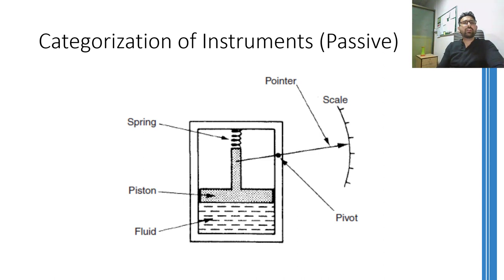The image shown over here is a schematic of another passive pressure measuring instrument. You can see that whatever pressure this fluid has will exert some force on the piston. This force will cause the piston to move against the spring and hence the pointer will move. This movement may easily be calibrated to show the pressure of the fluid. In this device, the pressure energy of the fluid is being converted to the kinetic energy of the pointer. Therefore, this instrument is using systems energy to measure the pressure. Hence, this is a passive device.